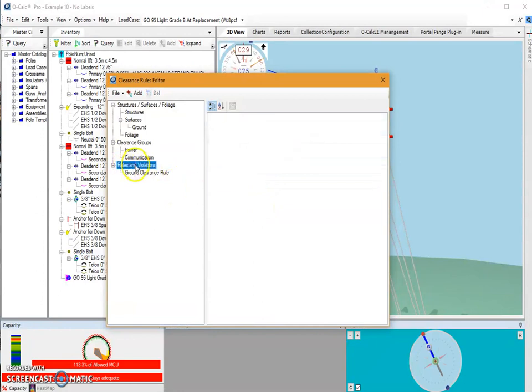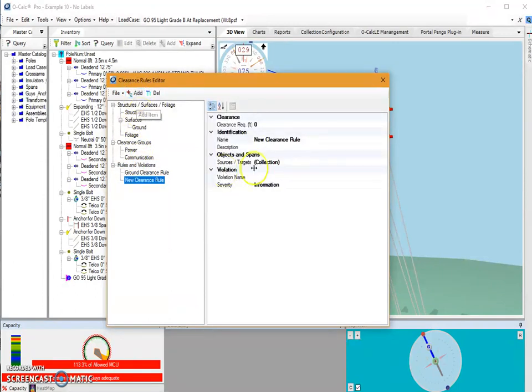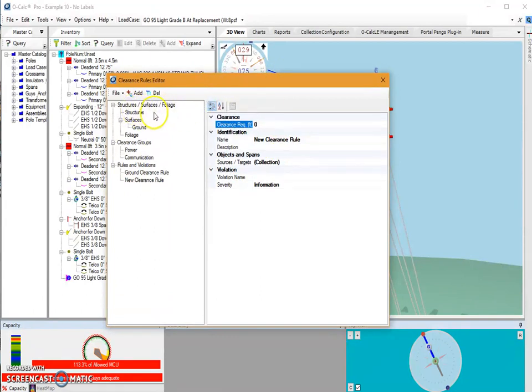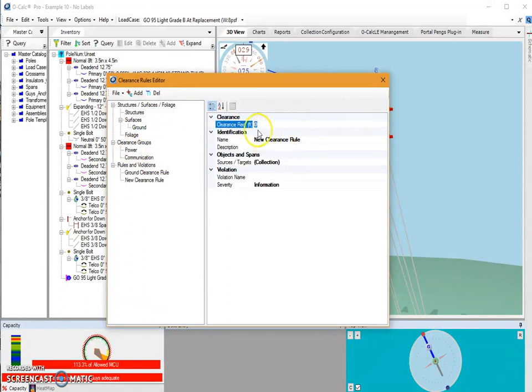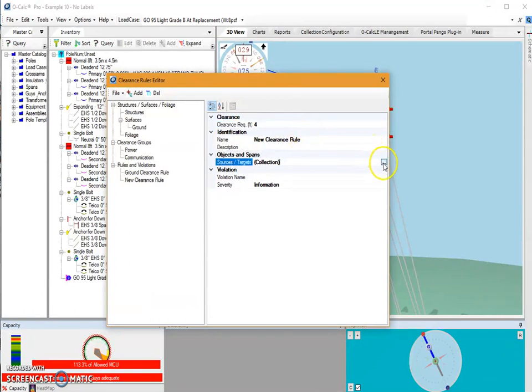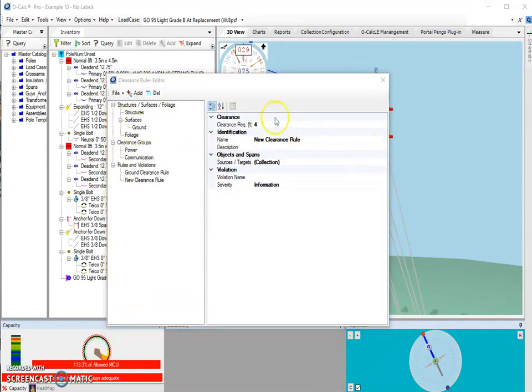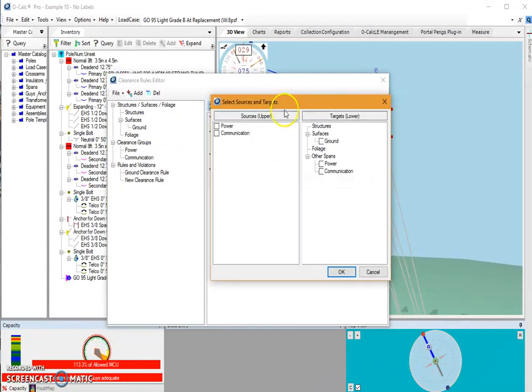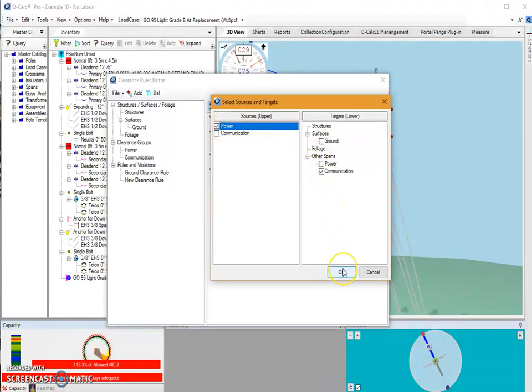An additional rule that I can add, if I select rules and violations and select add here, I will set this up to be the minimum distance between my power and communication spans. Let's say for argument's sake that there has to be a minimum of four feet between my power and my communication. So I will say that my power is going to be my upper and communication is going to be my lower. So I'm going to hit OK.